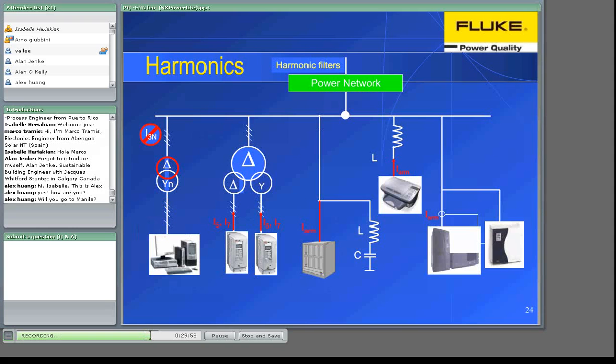In the second example, we simulate fifth and seventh harmonics, which will be stopped because the delta and the Y configuration at the secondary provide harmonics in counter phase. It means the fifth harmonics at the secondary of the delta and Y transformer will be in counter phase, therefore they will nullify one another.